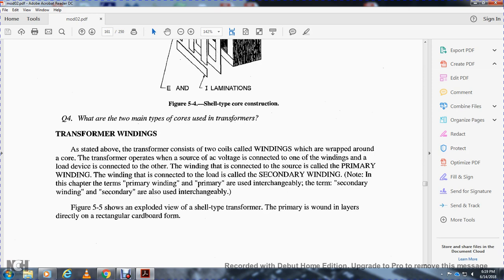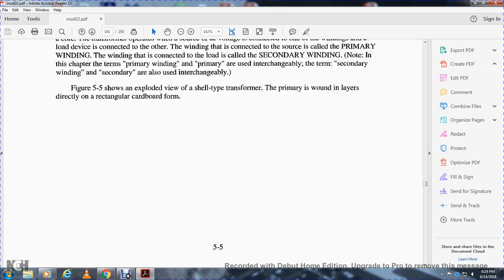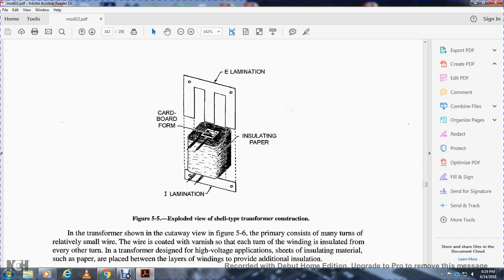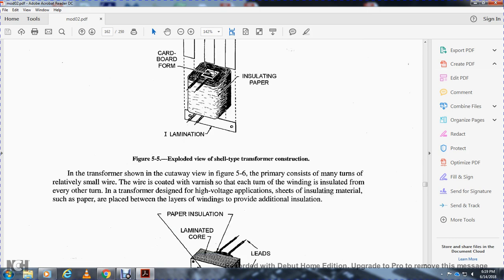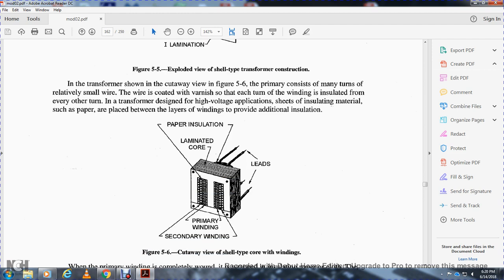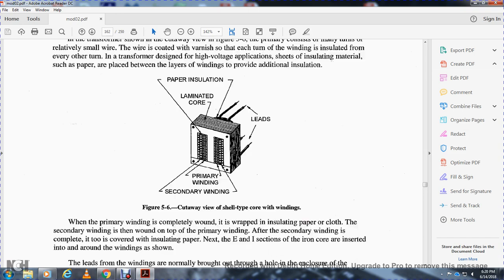Figure 5.5 shows an exploded view of the shell-type transformer. The primary is wound in layers directly on a rectangular cardboard form, with E-laminations, cardboard form, and insulated paper. Figure 5.6 shows a cutaway view. The primary consists of small wire coated with varnish, so each turn of the winding is insulated from the others. For high-voltage applications, sheets of insulating material such as paper are placed between layers of winding. Figure 5.6 shows the cutaway view of the shell-type core with secondary windings over primary windings, leads, laminated core, and paper insulation.